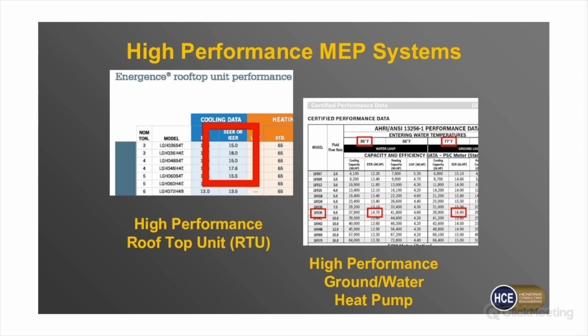So the way this manufacturer listed, they list the water loop if you're doing water source at 86, but they list the ground loop at 77. The reality is the difference between those two is the temperature. So if you had the ability to run your water loop colder, then the efficiency would go up. If your ground loop gets warmer, then your efficiency would go down, because the physics of that unit are the exact same either way, right? We're just riding an efficiency curve based on temperature. And you'll see the same thing for air-cooled equipment.